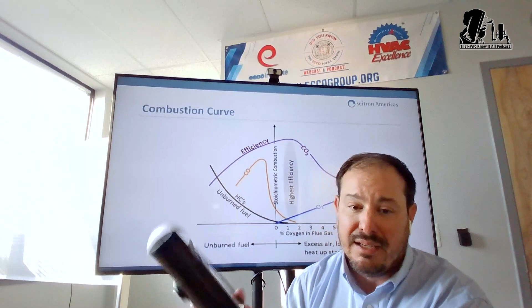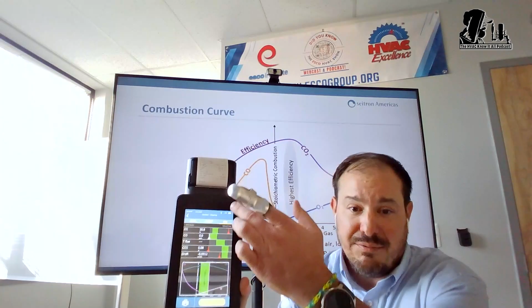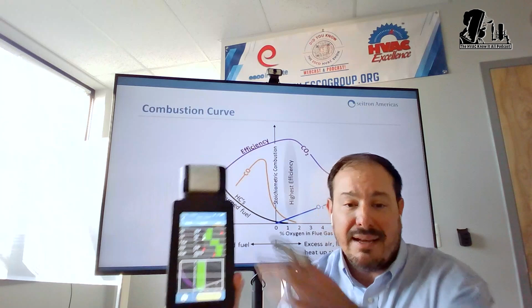So it's just where we're trying to land. Now, not to make a plug for my own analyzer, but I have to describe something. This is one of the reasons why we put that Pro mode on here, with, if you notice down at the bottom, the stoichiometric curve. Because if you set the boiler for the oxygen, CO, flue temperature, CO2, and all that in that green zone, which is the high efficiency zone, you'll be okay.